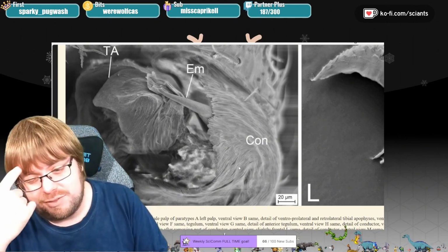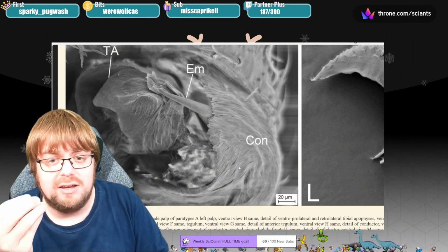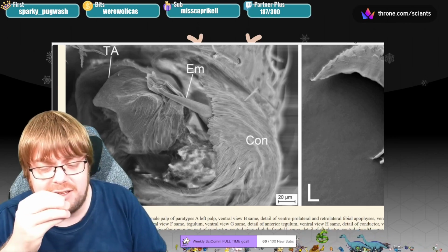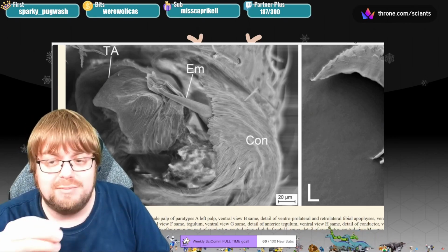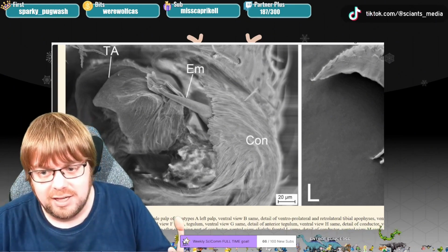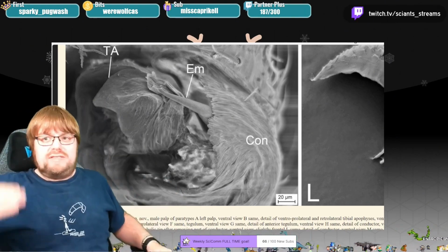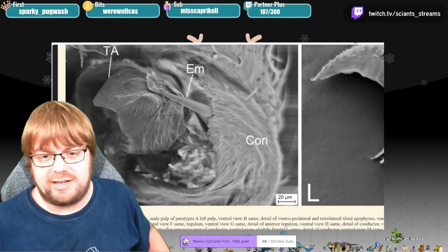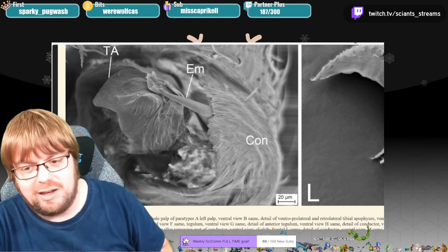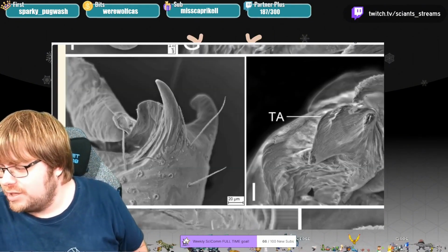The difficulty with that is the coating process is in a vacuum sealed chamber. The microscopy itself is in a vacuum sealed chamber. Vacuum sealing on its own, depending on how your specimens are mounted, could cause some damage too. So you don't necessarily want to be doing that process over and over and over again, because that could affect what you end up getting. Does that make sense?